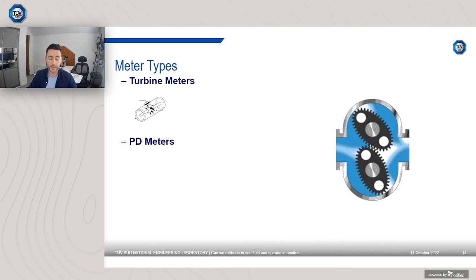What about PD meters? Well, again, it's very similar to turbine meters. You get liquid PD meters and you get gas PD meters, and they can only be used in the fluid that they were designed for. So liquid PD meters should be used in liquid, gas PD meters used in gas. So again, you cannot calibrate a gas PD meter in water, depending upon the components of which it was made.